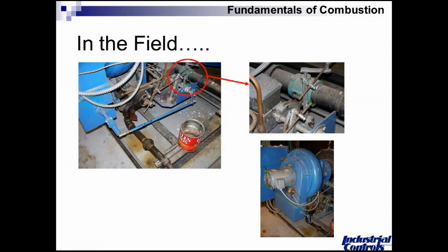You bring the analyzer around to the front of the boiler and you literally adjust set screws in that cam, which change the shape or contour in such a way that at any point in the boiler's firing rate, we have that desirable mix of fuel and air.